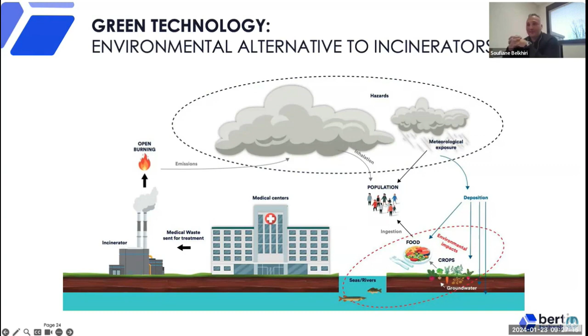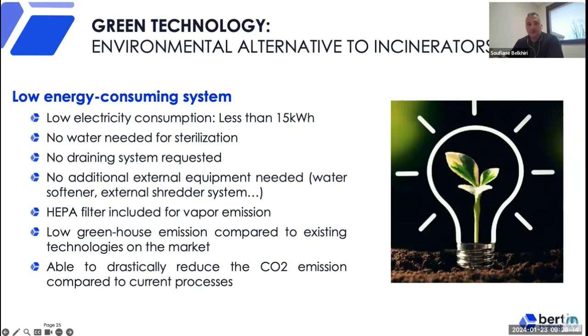Sterilwave is a green technology because it's a very low energy consuming system. It's a plug and play solution only using electricity, less than 15 kilowatt hours. We don't need any water for sterilization, and we don't need any draining system to run this machine. Furthermore, we don't need any external equipment, such as a water softener or external shredder system, to make the machine run. We do propose a HEPA filter for vapor emissions, because microwave technology is basically a dry heat solution, converting moisture into steam. It's a low greenhouse gas emission technology compared to existing technologies on the market, and it enables any government, any country, any hospital in the world to drastically reduce CO2 emissions compared to the current process.